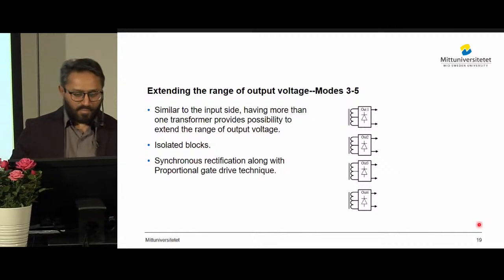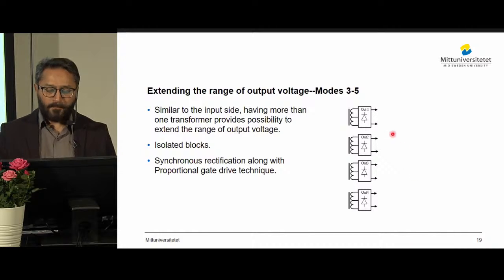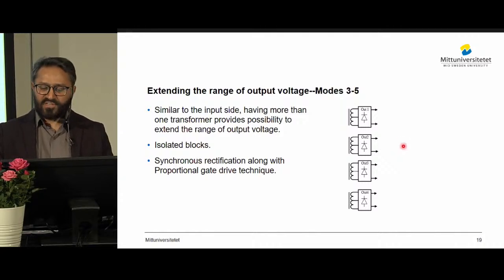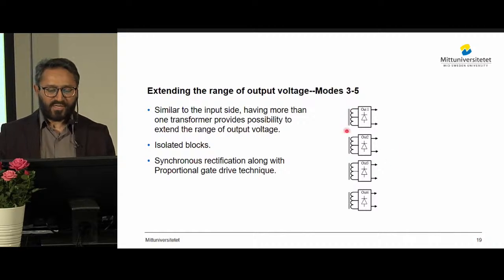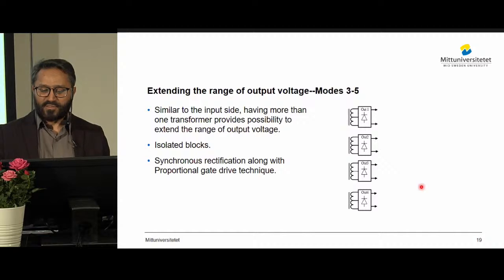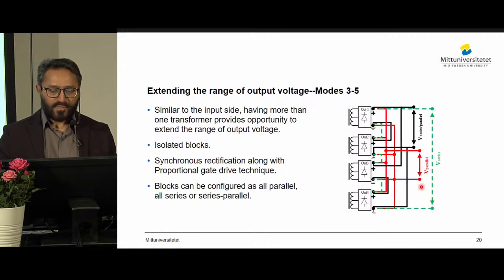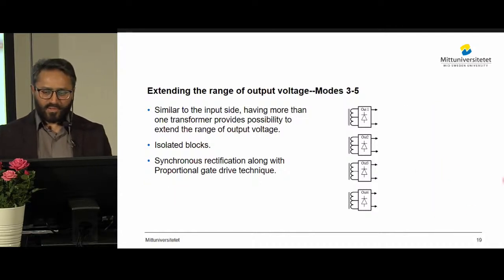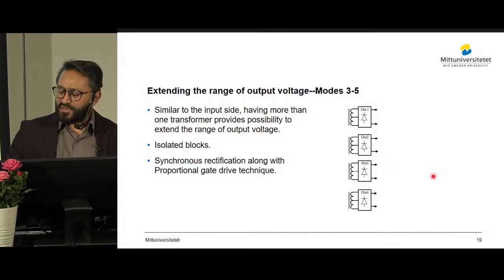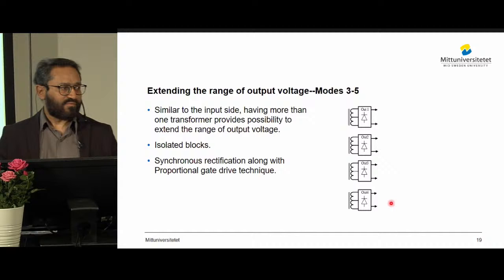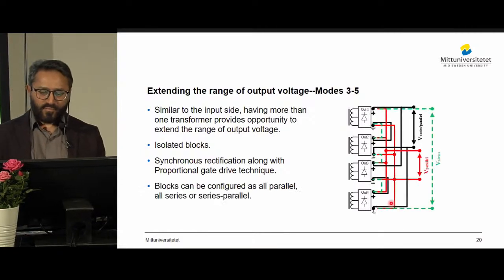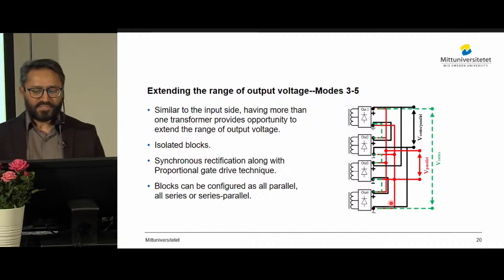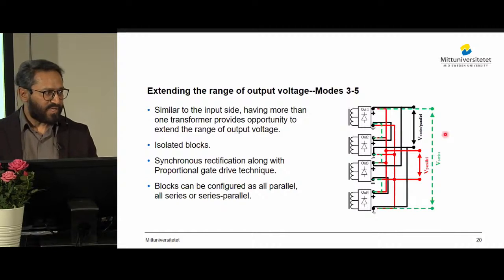Similar to the extended range of supply voltage, the provision of several transformers makes it possible to extend the range of output voltage. One way to achieve this is if the secondary windings of all 4 transformers could be made electrically isolated from each other. This can be achieved by performing rectification of each transformer's secondary voltage in such a way that it generates an electrically isolated block for each transformer. Once we get isolated blocks, they can be arranged either all in series, in parallel, or in a combination of series-parallel connections.